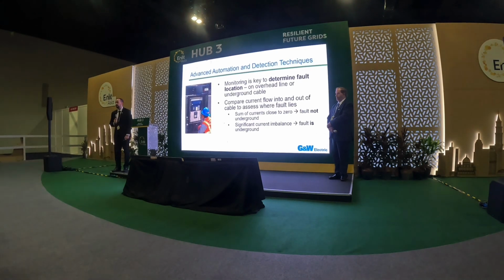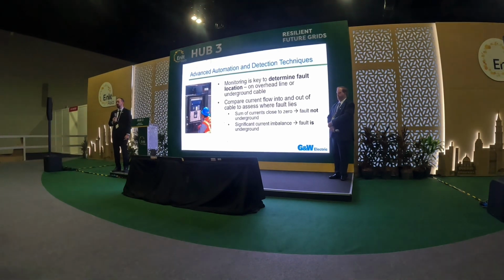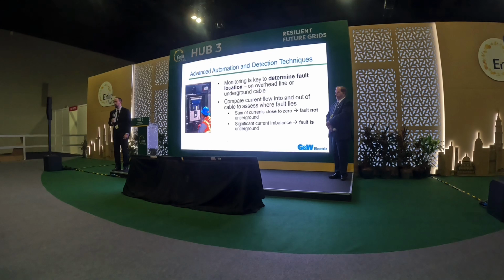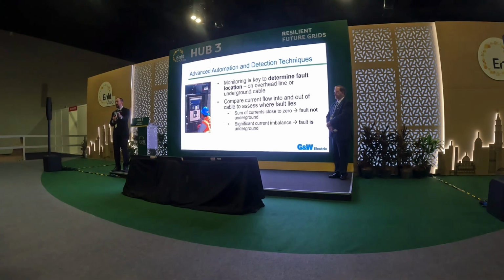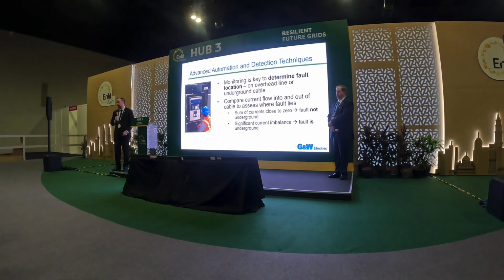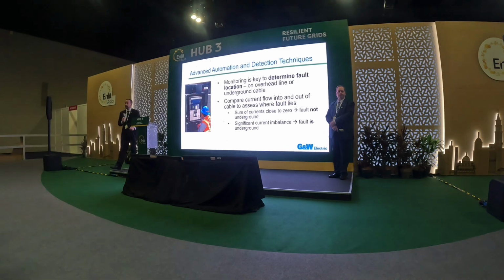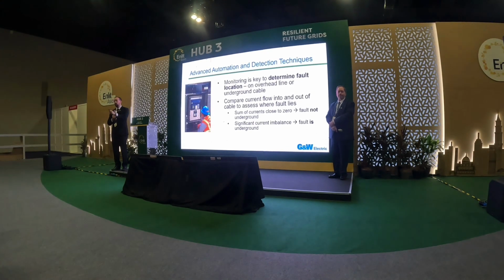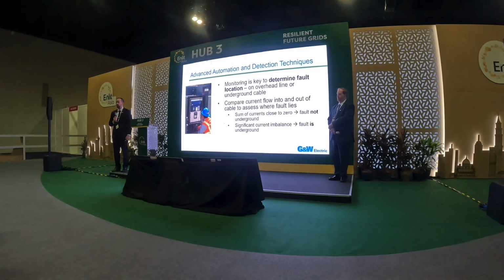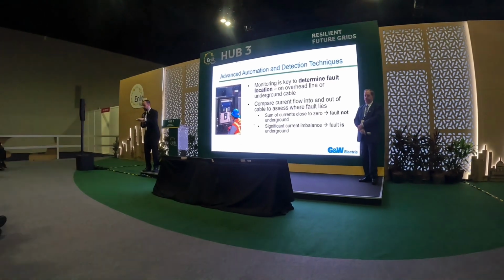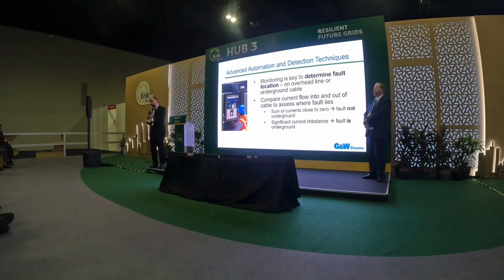By doing that, they were simply able to take advantage of digitalization techniques and use their relays and their SCADA system to communicate information back and forth between those two devices. A differential protection scheme is essentially looking at the section between those two devices, and if the currents are more or less equal, we know that the fault is not in that section, okay? If they see an imbalance or a difference between the readings on those two devices, they're able to identify with high confidence, yes, we have a fault on our underground circuit.